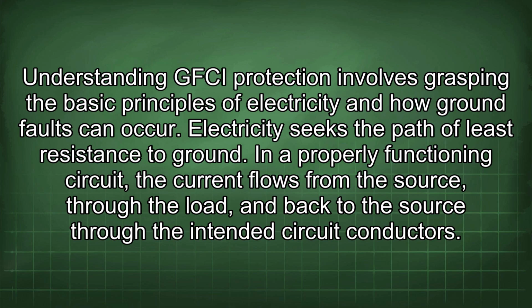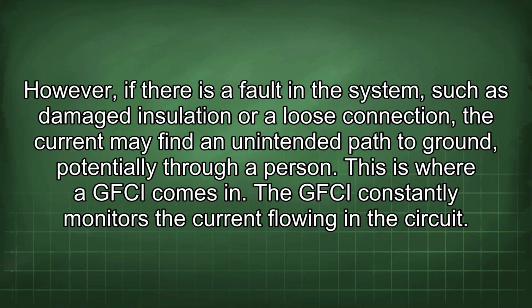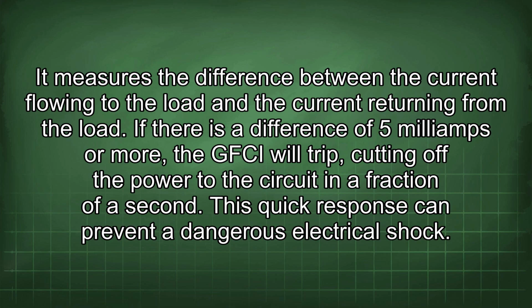Electricity seeks the path of least resistance to ground. In a properly functioning circuit, the current flows from the source through the load and back to the source through the intended circuit conductors. However, if there is a fault in the system, such as damaged insulation or a loose connection, the current may find an unintended path to ground, potentially through a person. This is where a GFCI comes in. The GFCI constantly monitors the current flowing in the circuit. It measures the difference between the current flowing to the load and the current returning from the load.